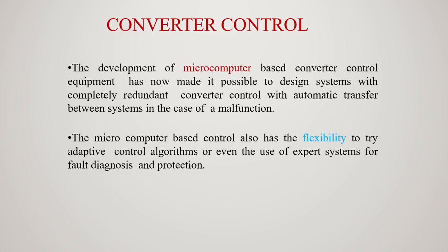Now let us see converter control. Development of microcomputer based converter control equipment has now made it possible to design systems with completely redundant converter control with automatic transfer between systems in case of a malfunction. Not only is the forced outage rate of control equipment reduced, it is also possible to perform scheduled preventive maintenance on the standby system when the converter is in operation.